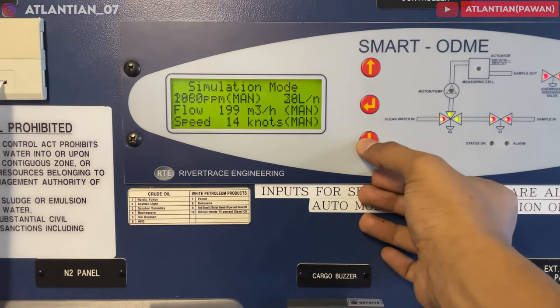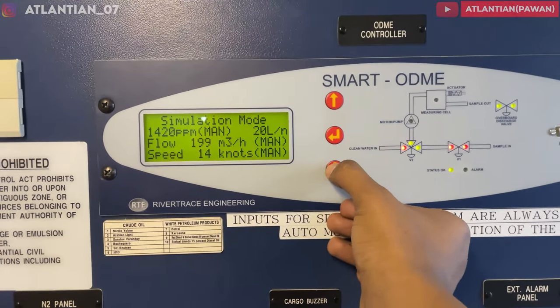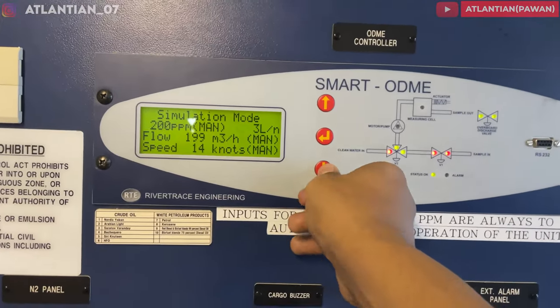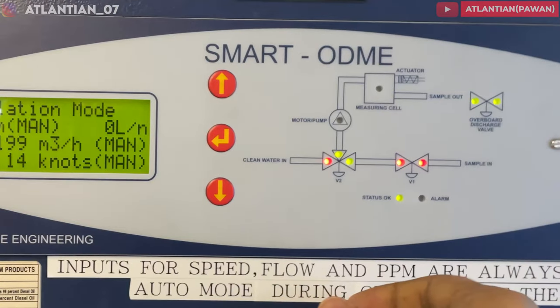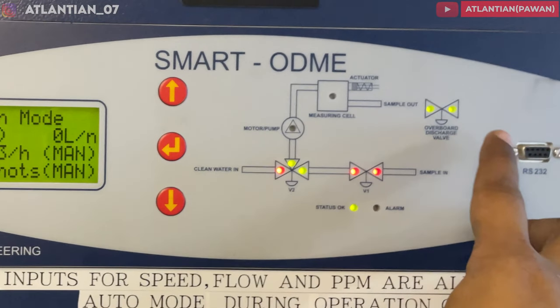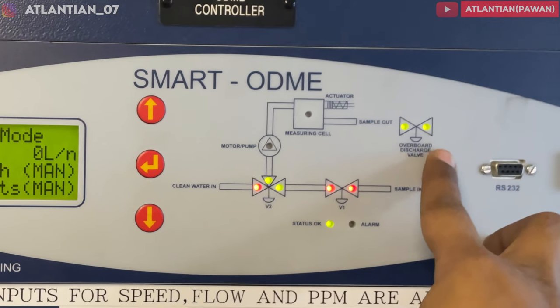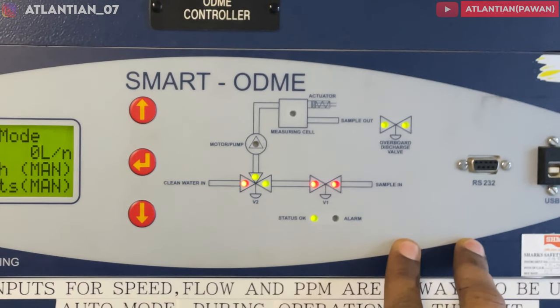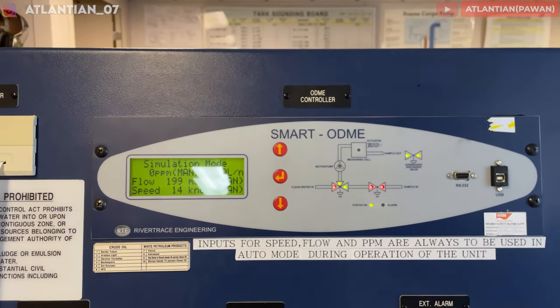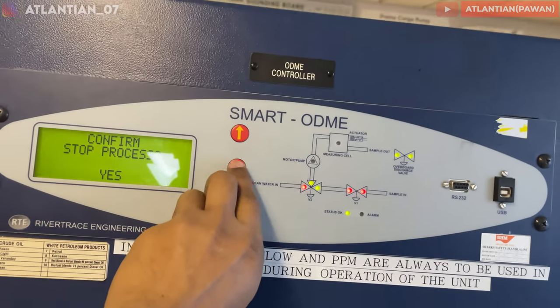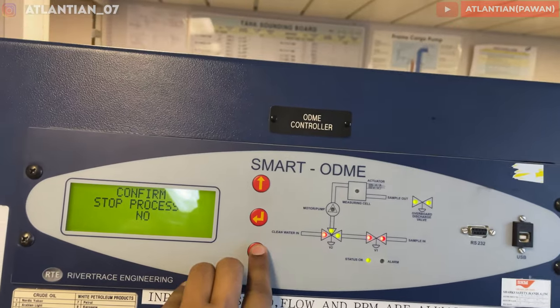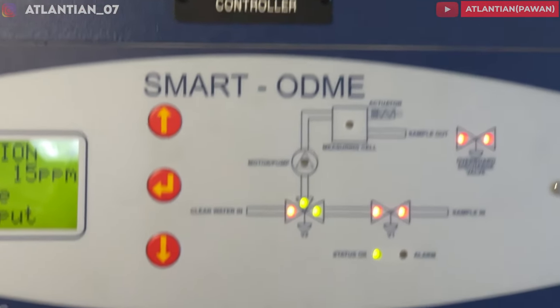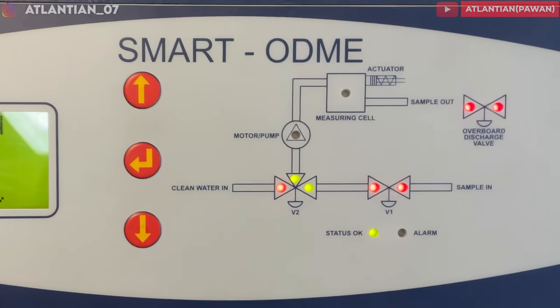Now I'll bring the value back down. Once it is below 30 liters per nautical mile, you can see the overboard valve is open again. I'll bring it back to zero — the overboard discharge valve is still open. This is what we have to check: whether our overboard discharge valve is closing and opening at the right intervals when we enter the correct values. Once done with the test, I'll click close — and the overboard discharge valve is now closed. That's the simulation test.